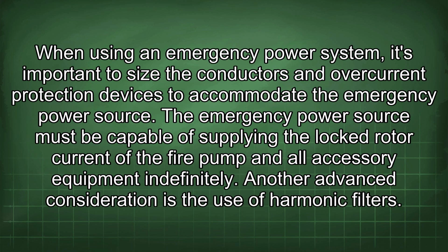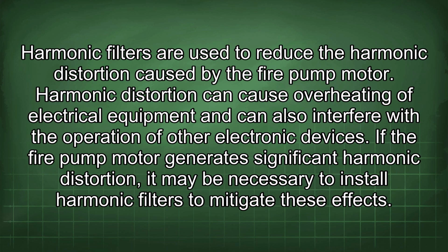When using an emergency power system, it's important to size the conductors and overcurrent protection devices to accommodate the emergency power source. The emergency power source must be capable of supplying the locked rotor current of the fire pump and all accessory equipment indefinitely. Another advanced consideration is the use of harmonic filters. Harmonic filters are used to reduce the harmonic distortion caused by the fire pump motor.